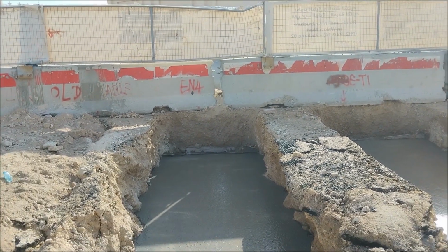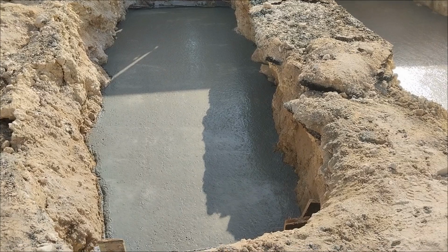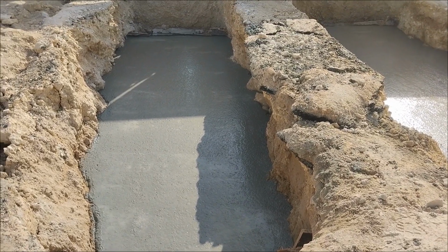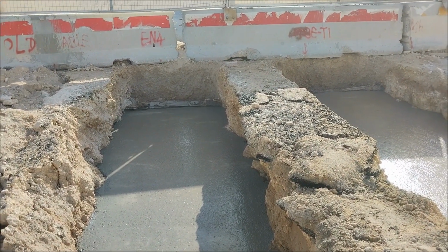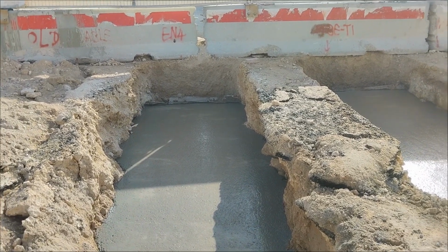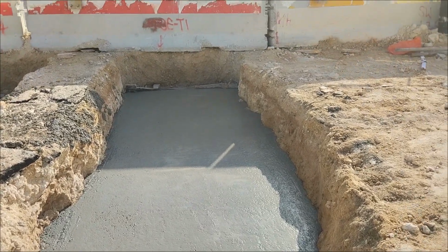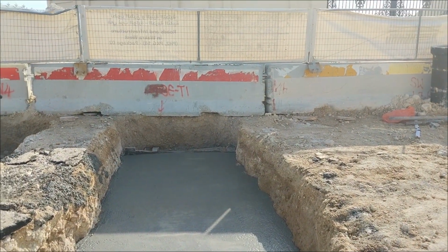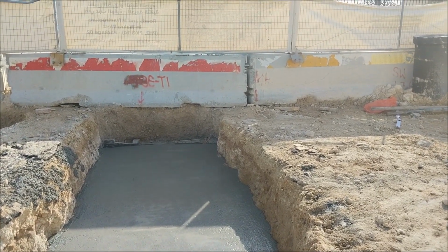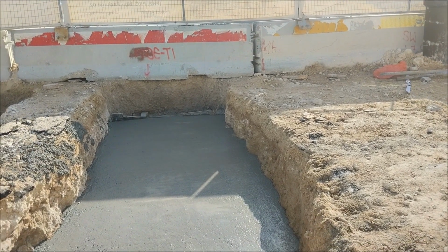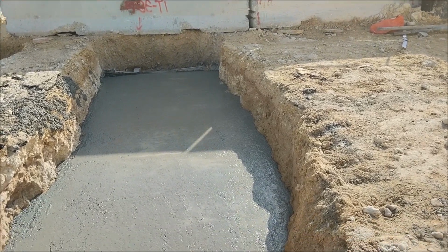Normally, the concrete surrounding should be 150 mm around all the pipes, and at least a 5 cm gap should be provided between each pipe. Spacers should be used for this. As you can see here, the concrete is already cast in this area. After this, the concrete duct will get bitumen coating, and warning tape will be installed. This is another duct, as I showed in the previous clip, the road crossing duct here. This also has concrete surrounding completed.